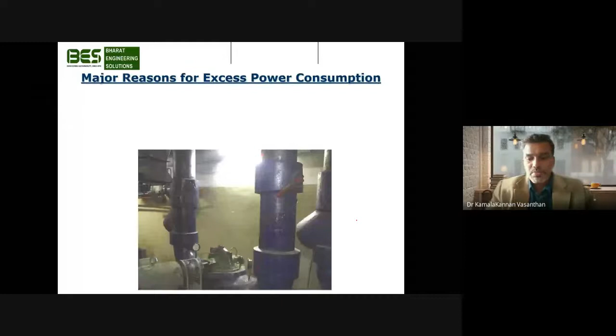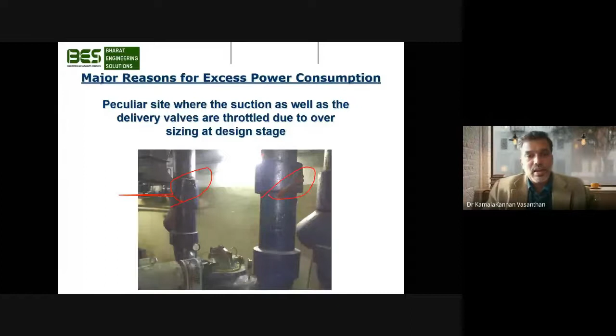If you're able to see here, both the inlet and outlet pipes of these pumps have been throttled. It's mainly because the pump is oversized against the actual requirement at this site. So the pump is throbbing, the mechanical seal is continuously wearing out, and the impeller is getting replaced every time. When we visited this site, immediately what we did was throttle the valve, no other go, because if not, he has to replace the whole pump. And we replaced this pump with almost half the kilowatt size of the pump that was at the site.